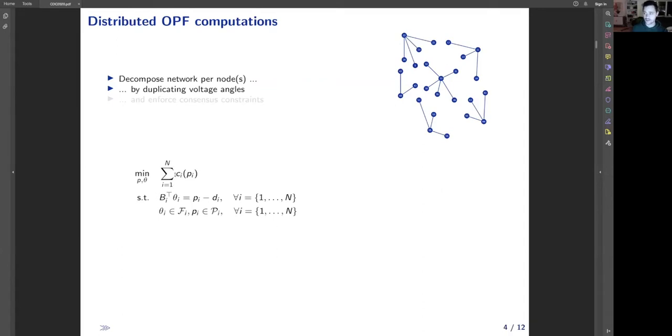The original problem can be separated such that the objective function is separable per node, and nodal power balance constraint and flow and generator limits also become node specific. To restore the connectivity of the graph, one needs to enforce consensus constraints that require the voltage at neighboring nodes to match the same consensus value, such that every node tries to update its voltage estimates towards the consensus variable.